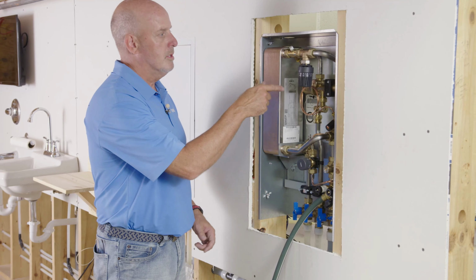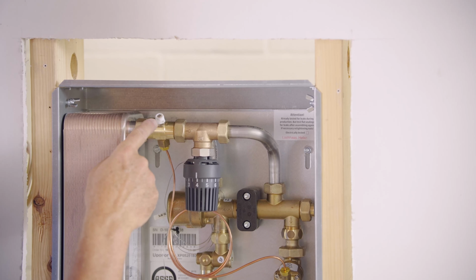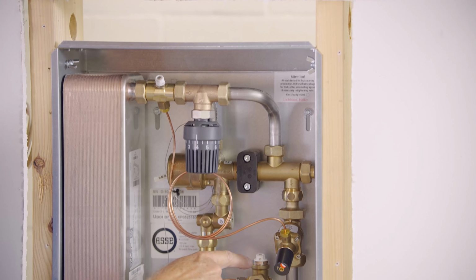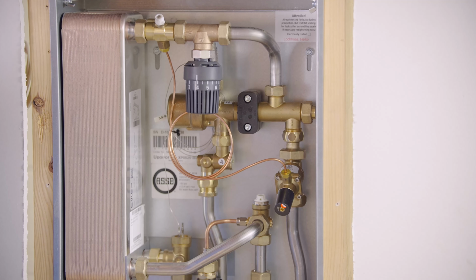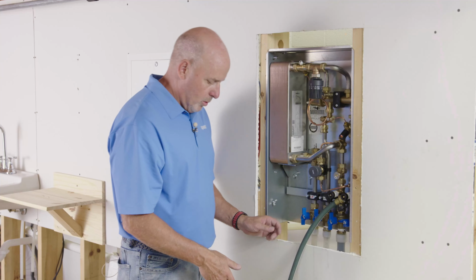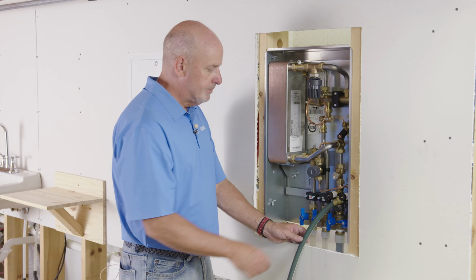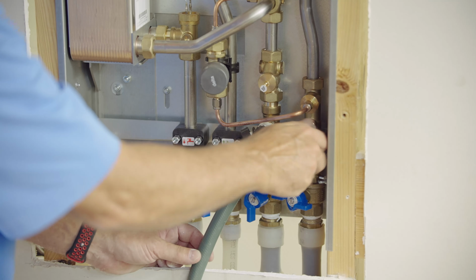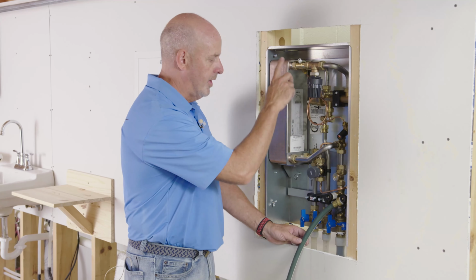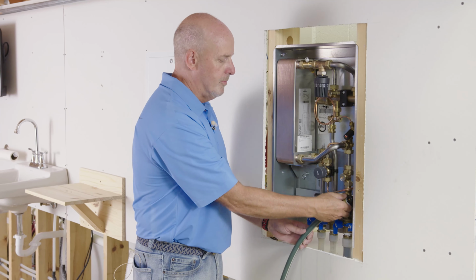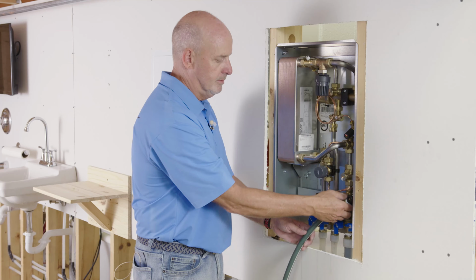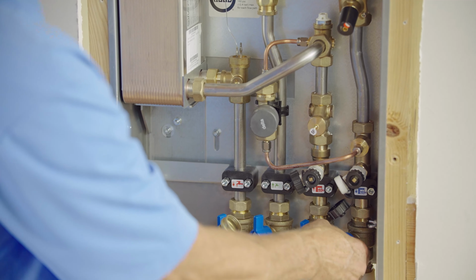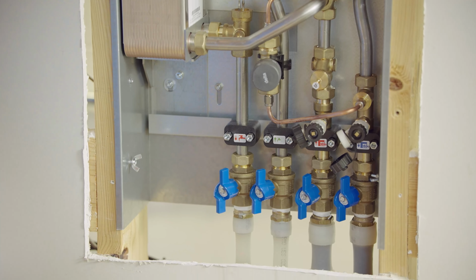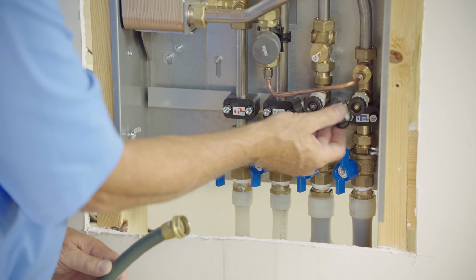If needed, to make sure you get all the air out, the upper valve can be opened along with the lower valve to make sure any entrained air is removed from the system. Once we have a steady stream of water in the bucket, we can close the valve, make sure our vents are closed, remove our drain line, open up the hydronic return line, and the port is ready for operation.